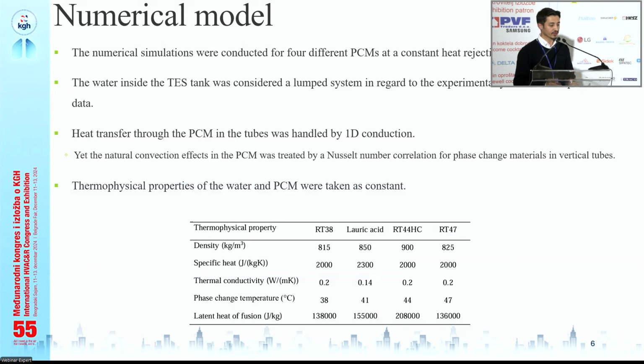The water inside the thermal energy storage tank was considered a lumped system with regard to the experimentally obtained data, because in the experimentation we observed that the temperature did not show significant change with respect to location, as we measured the temperature in axial and in radial directions. Therefore, we didn't see much difference. Besides, the heat transfer through the PCM in the tubes was handled by one-dimensional conduction, yet natural convection effects could occur once the PCM liquefies, because the liquid can move up and down, circulating due to density variations. However, we treated this by a Nusselt number correlation established for phase change materials in vertical tubes, which is appropriate for us.